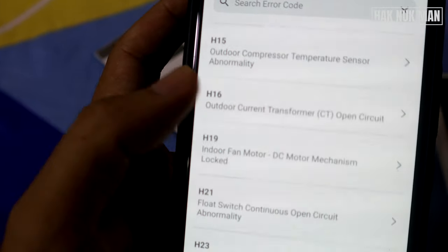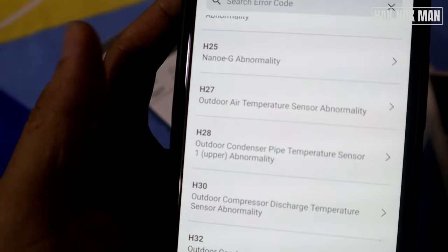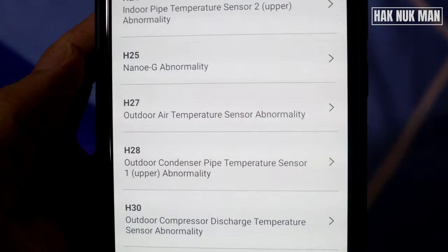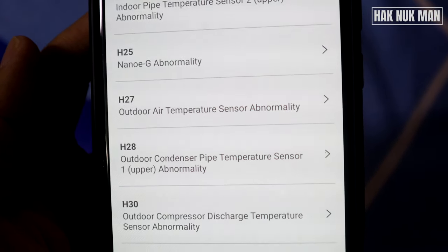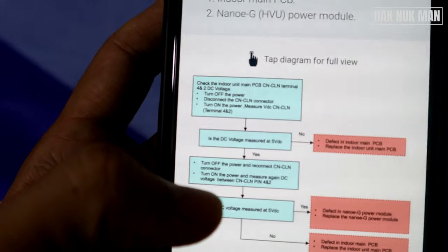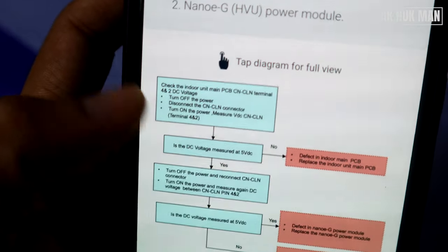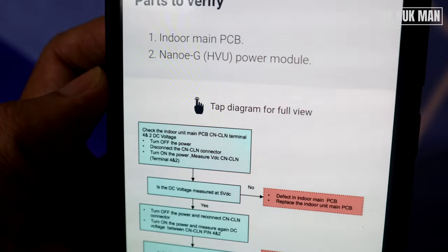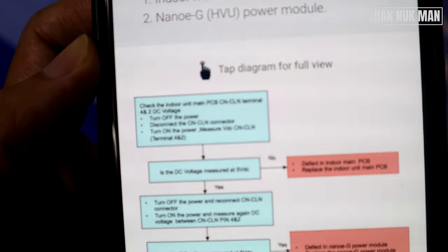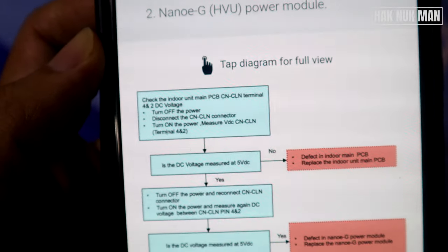H00 means no abnormality detected. As you can see on your remote control, it has the error code list. For example, H25 is nanoE-G abnormality. If you want to know what the problem is and what to do, just press on each error code and it will show you what to do — for example, indoor main PCB, nanoE, nanoE-G, HVU power module — and you can read all the information and checklist steps on the page.